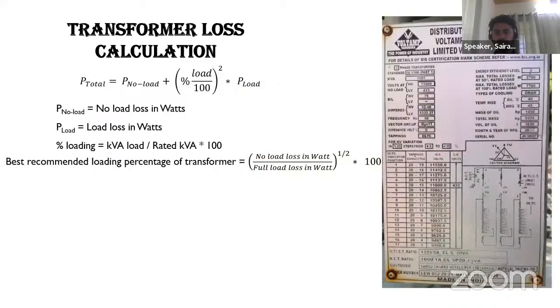I have presented here a nameplate detail of a transformer, in which you can see in the right corner that the energy efficiency level is 2, and the maximum total losses at 50% rated load and at 100% rated load are given on the nameplate itself, with the load loss and no load loss, like core loss and copper loss, together. We have a formula that the total loss is equal to the no load loss plus the percentage of load squared times the load loss. With this, we will get the total loss of the transformer.